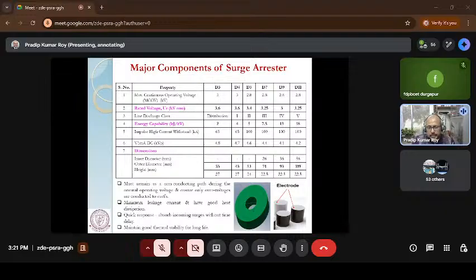Okay, but if you look at the thickness of the block, if the thickness is very high, that means the rating of the block is also high. That means if I need a high rating, normally we increase the thickness of the block. So if you remember the previous slide, I need a 400 kV surge arrestor, which means I need 133 blocks. Now if I want to increase the rating of the block, you can increase the thickness, but if you increase the thickness, again the height of the surge arrestor will increase. So I need the same thickness and the same size but a different rating. I have to increase the rating of the block.